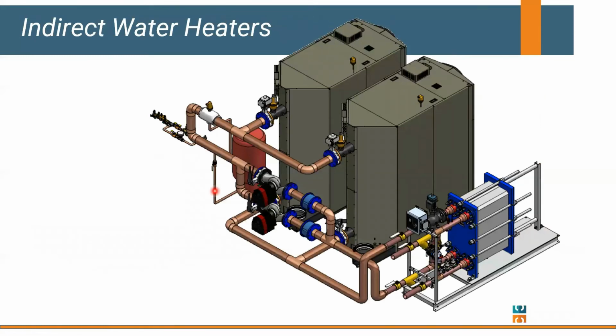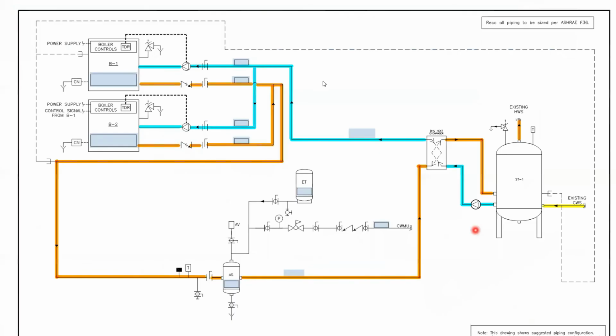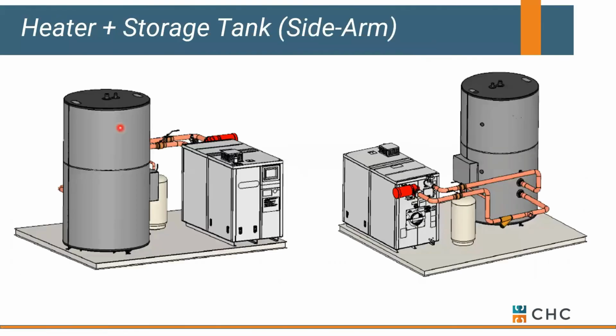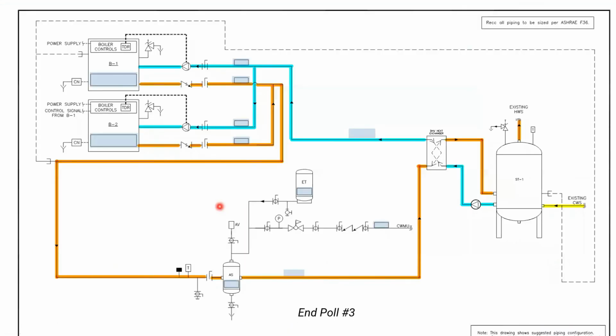Now, you can take boilers and heat domestic water, but the only way to do that is by separating it. So typically you've got a heat exchanger or an indirect coil in your storage tank. Okay, so boilers are chemically treated. You can heat a storage tank, but you've got to separate it with the heat exchanger. Okay, you could heat your system. You could put domestic priority on this if the tank gets cold. There's ways to do this, but these are boilers, and these water heaters. Okay, not to beat a dead horse. Let me end my poll and we'll share results.